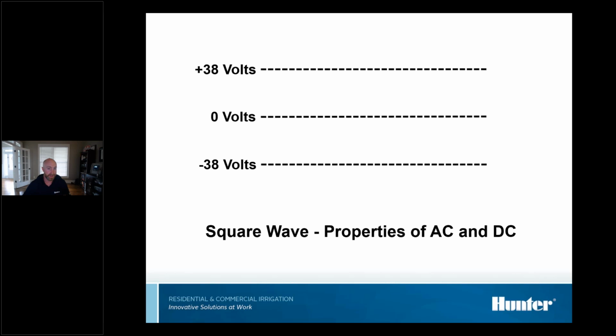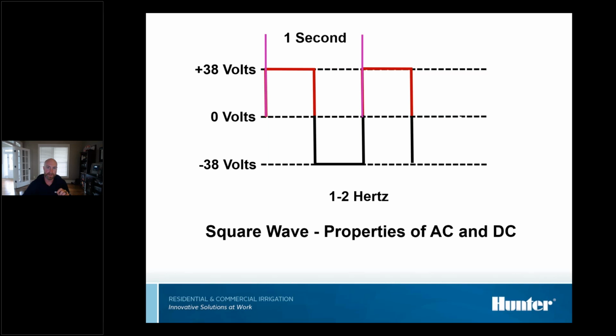Comparing that to a two-wire controller, you've got what we call a square wave. You've got 38 volts positive that it stays at for a certain period of time, and then 38 volts negative that it stays at for a certain period of time. It reverses itself like AC power, but it stays at the same voltage—it doesn't have this constant drop like a sine wave. It stays at the same voltage for a certain period of time, and it rotates like that only 1 to 2 times per second, so 1 to 2 hertz.